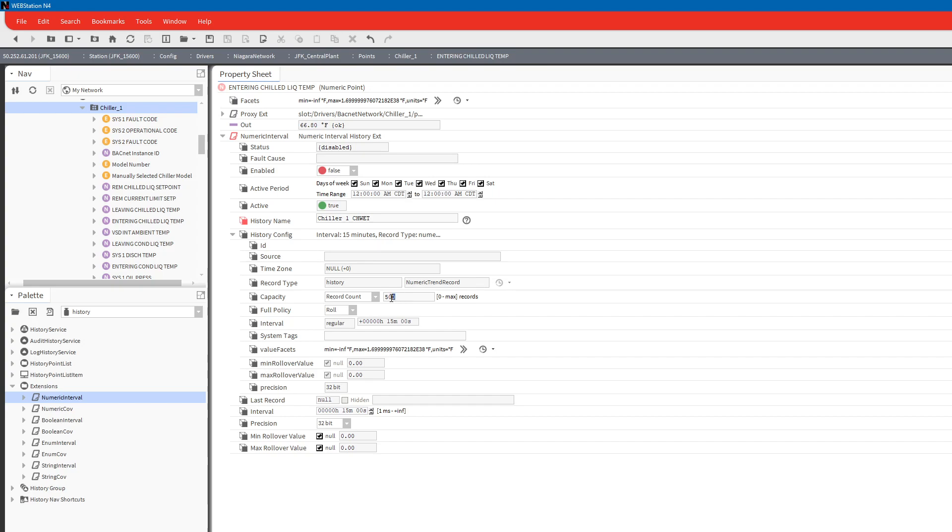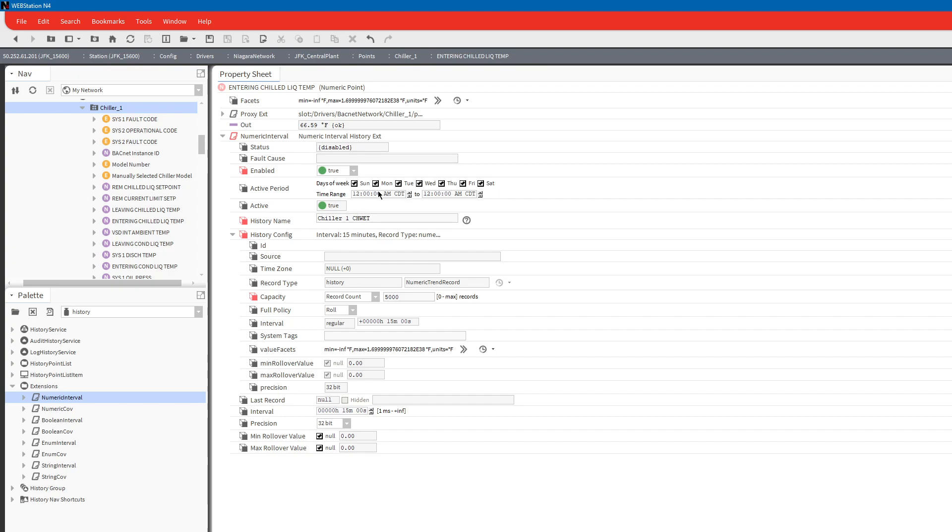We're going to have it do a count every 15 minutes. You can expand that out to 30 minutes, 60 minutes, I wouldn't go more than 30. We've had some where we had to do it every five minutes because we had something going on we couldn't quite catch it. On something like this want the record count to be a little bit higher so we can see a longer period of time. You can do whatever your memory on your computer will allow. On the Jace you don't want to do too much because then you start using up the memory which will slow it up.